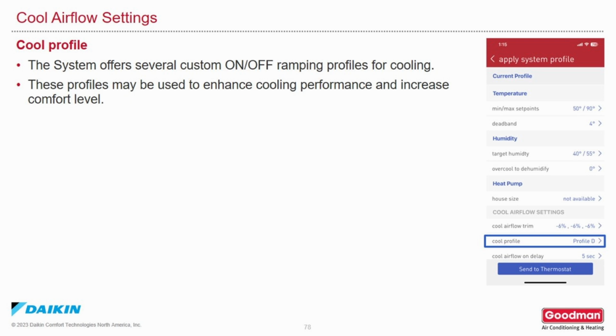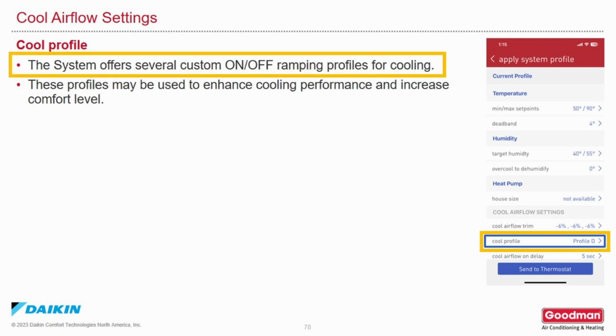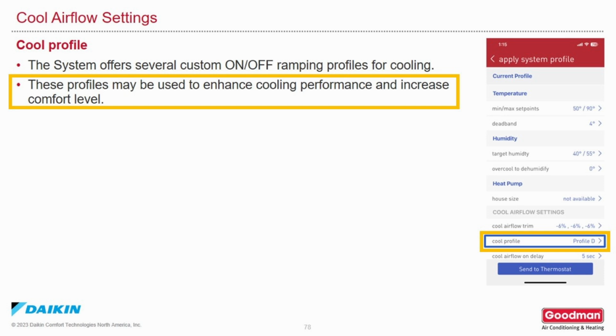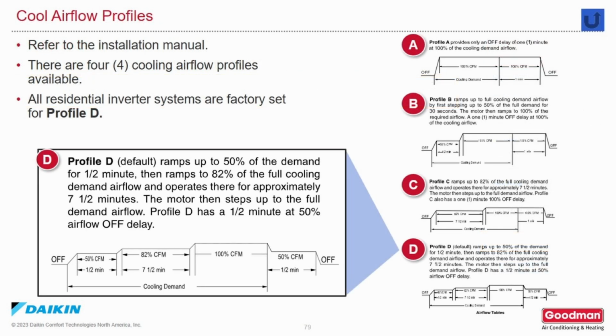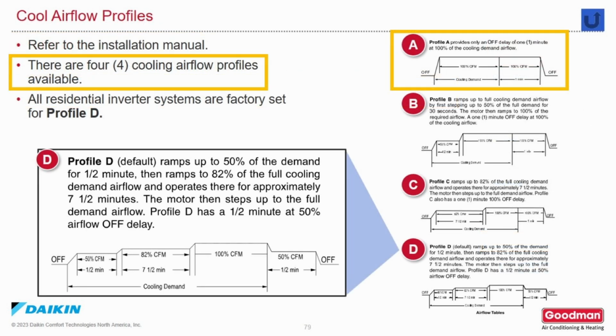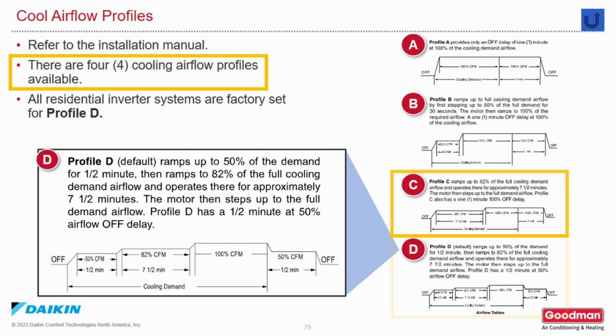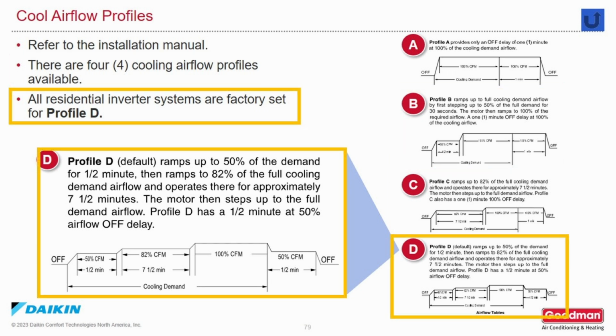The system offers several custom on and off ramping profiles for the cooling mode. These profiles can be used to enhance cooling performance and increase comfort level. For cooling airflow profiles, refer to the installation manual. There are 4 cooling airflow profiles available. All residential inverter systems are factory set at Profile D. All of these profiles can be found in the installation manual.